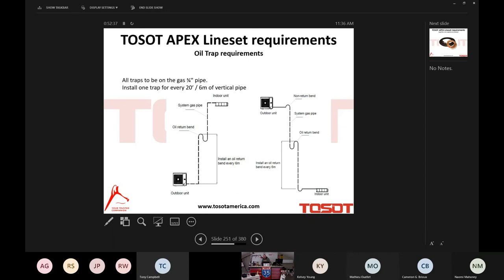And as you can see in the picture here, this does not matter if the outdoor unit is above the indoor unit and vice versa. You see, with the mini splits, it makes a difference, baby, right? In the mini splits, if the outdoor unit is above the indoor unit, you've got to trap. That's the only time. But in the Apex world, we are trapping no matter what the scenario, whether it's the outdoor unit or the indoor unit above. If that vertical separation is 20 feet or more, we're trapping, right? Simple as that.